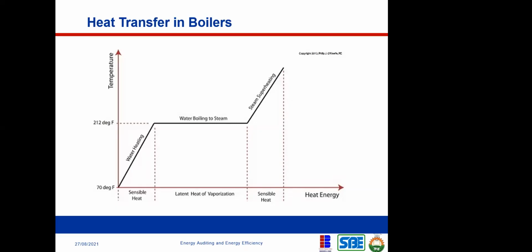So just to make us understand what is happening in a boiler, I explained this yesterday. You have water that you heat. Assuming that you have just water at normal room temperature, say 70 degrees Fahrenheit, and then you start applying heat to it. The heat that you're applying to that water at that time is sensible heat. That water will continue to heat until it gets to 100 degrees centigrade. When it gets to 100 degrees centigrade and you keep applying the heat, it's not going to increase in temperature anymore. What's going to happen at this time is that it's going to use the higher heat that you're applying to change its phase. It will now change into gas, which is what we know as steam.